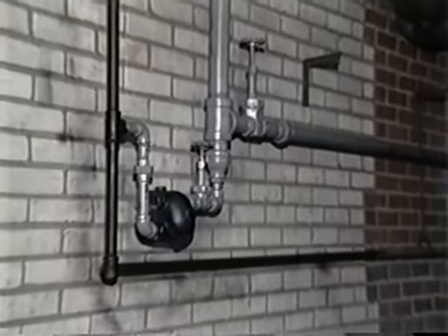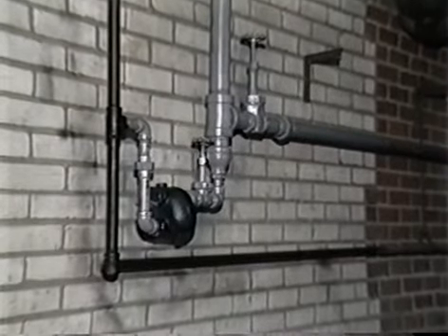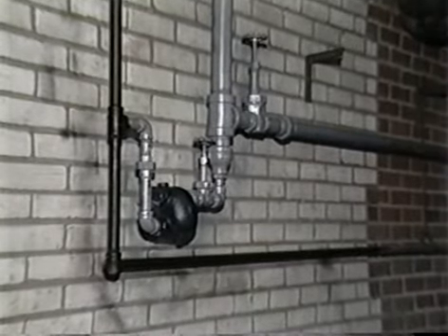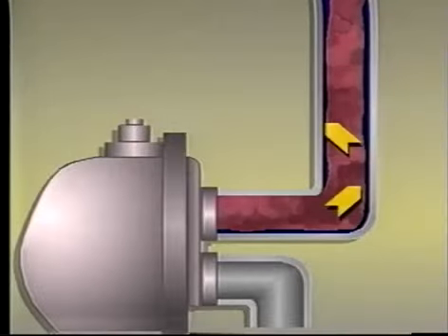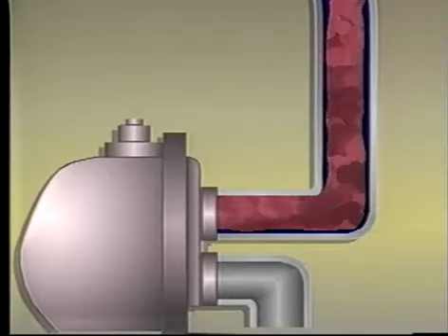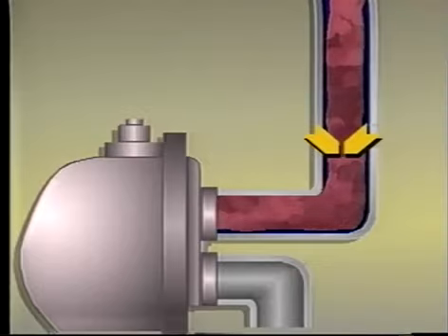Differential shock can also become a problem when elevated heat exchange equipment is drained with a substantial vertical drop ahead of the trap. Under normal conditions, condensate drains down the walls of the pipe. A sufficient volume of steam constantly flows down the center of the pipe to replace the steam that is condensed by radiation losses of the piping and the trap body itself.